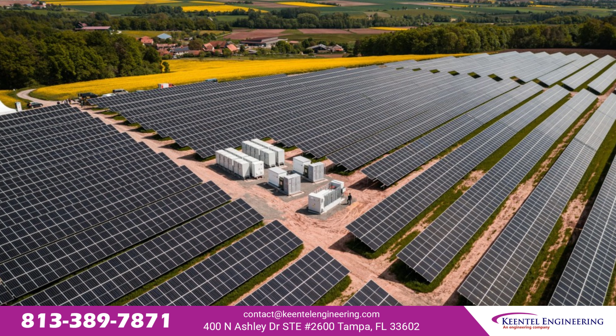The challenge: a 300 megawatt solar plant partially tripped during a disturbance, traced to overly sensitive inverter protection and non-compliant ride-through. Keentel ran electromagnetic transient simulations and fault replay modeling, validated inverter control logic against PRC-024 curves, then adjusted the ride-through curves and frequency thresholds, and resubmitted updated models to the ISO. The result: full PRC-029-1 compliance, nuisance tripping eliminated, and improved grid stability contribution.